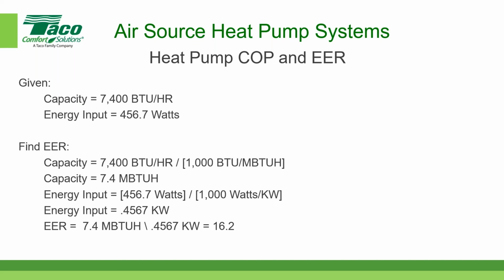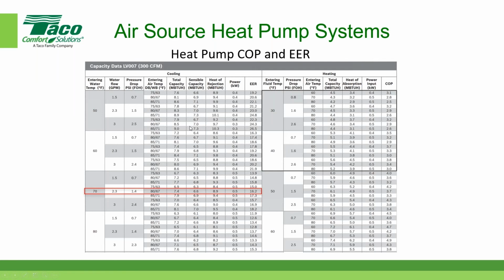And in some of the charts that are out there, here it is right in front of you. Here's a chart from one manufacturer. If you notice this column over here, it's the calculation that we just did. There's the EER, and there's the value that we calculated. It has an output capacity, the total capacity, of 7.4, or 7,400 BTUs per hour, or MBH. 7.4 divided by 0.5, and they rounded up, by the way, when they made this chart. The actual number is what I said a moment ago.